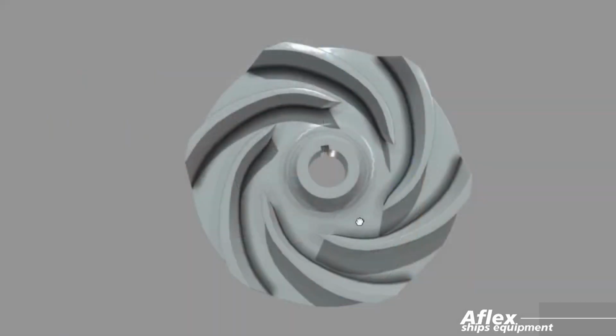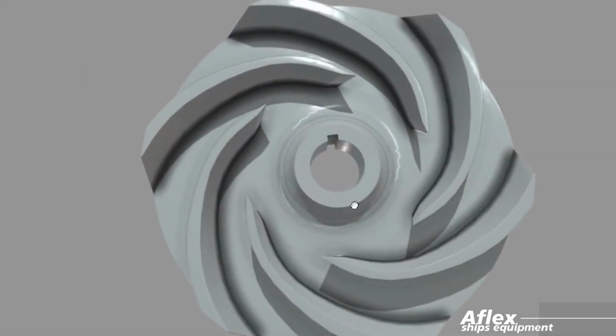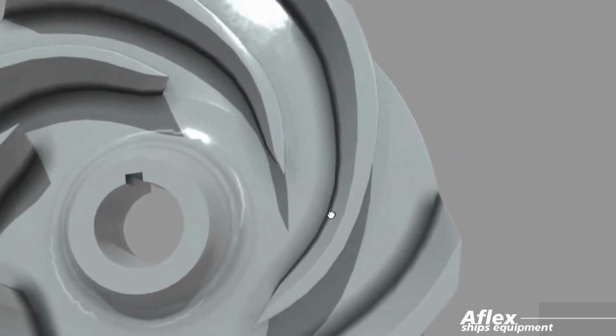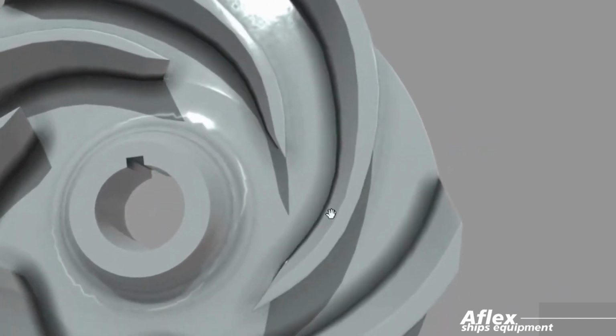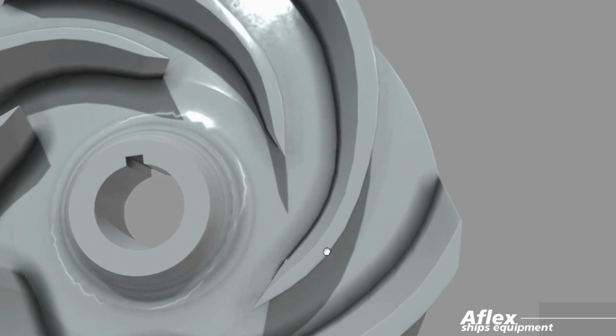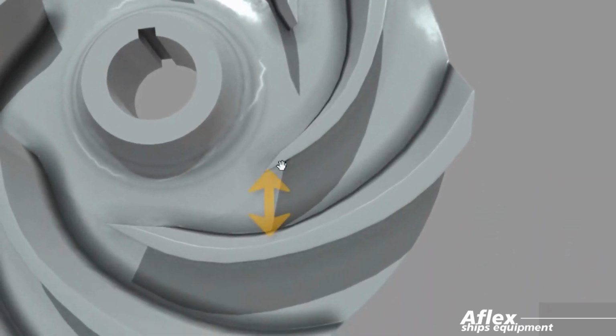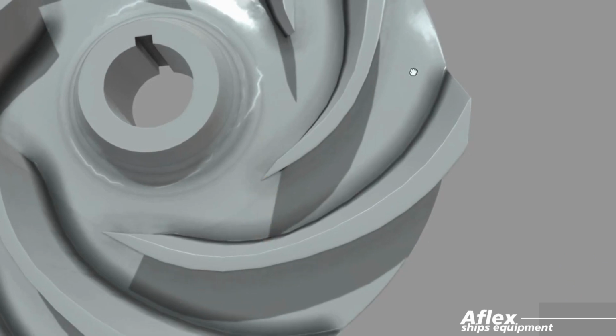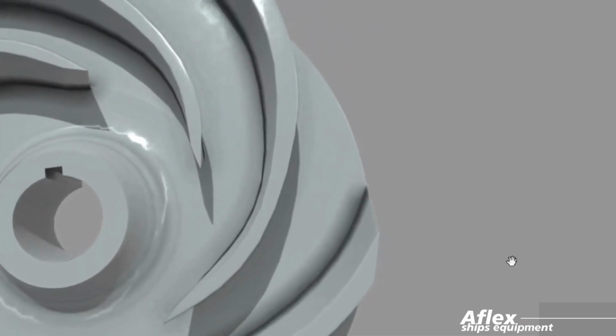Notice that each of the vanes has a gradually increasing gap between it and its neighbour. For example, we can see here that the gap is quite small, and when we get to the outer periphery, the gap has become quite large. This change in dimension is the reason the impeller can change velocity to pressure.